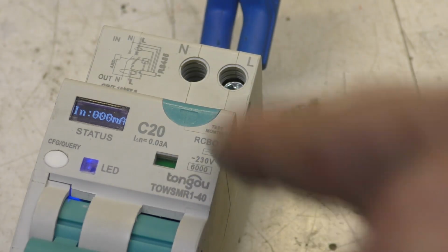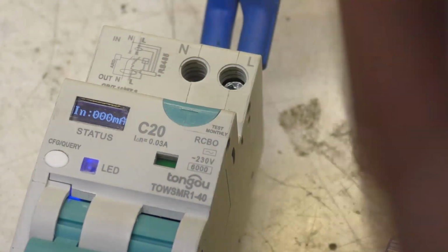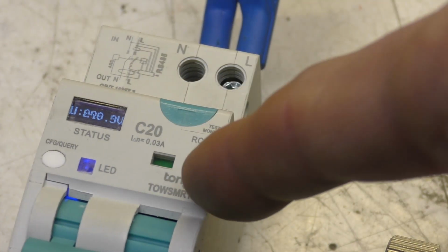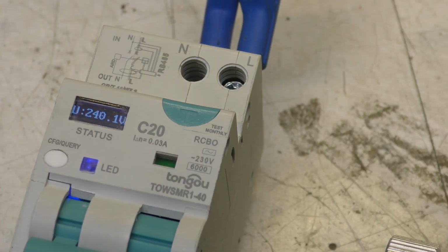One thing I'd need to check: if that test button is putting a resistor across the load, does pressing and holding that likely burn out the test resistor? An RCD test resistor is normally rated expecting the thing to trip as soon as you press it. Now if you can press that and it never trips, is that going to just burn that resistor out?